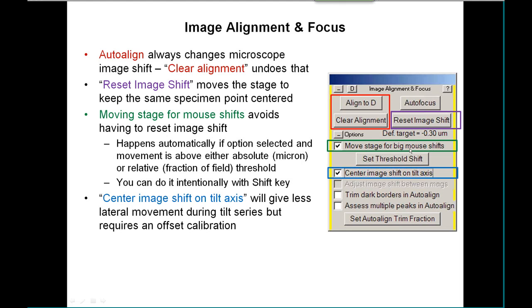When you've taken an image, you can right-click and shift it to wherever you want, and it will change the microscope image shift, and the next image will show up superimposed on the position you've moved to. Reset Image Shift will zero this out and change the stage position as well. If the option to move stage for big mouse shifts is enabled, then when you do these right mouse shifts and they are big enough — either in absolute terms or as a fraction of the field — it will move the stage instead of the image shift. Even without this selected, you can make this happen intentionally by doing the shifting with the Shift key held down.